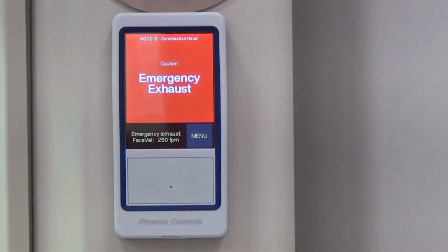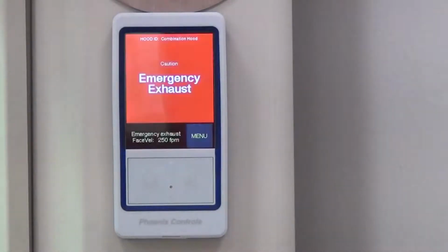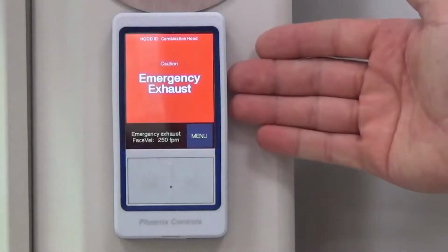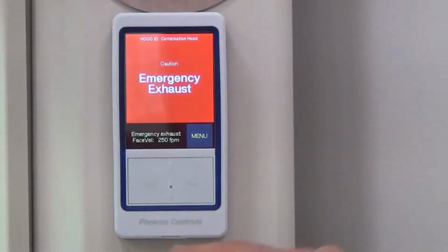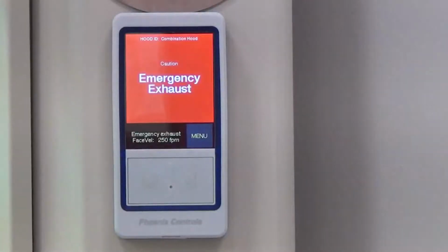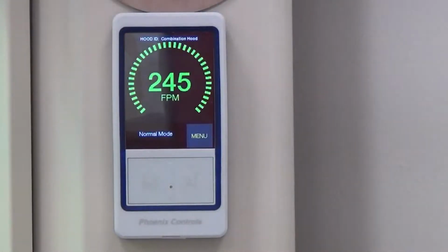Now the reason we did this is if a customer has a chemist or somebody inside of the lab that has a question about why their fume hood has a high flow, most times they would have to call a maintenance guy. He would have to go into the building automation system to be able to pull up that point from this fume hood monitor and say, yeah, that's an emergency exhaust. Now the user can very clearly see this fume hood is in emergency exhaust. I need to take it out of emergency exhaust so that it will return to its normal flow. And then as the face velocity drops back down to normal, you can very clearly see that on the screen.